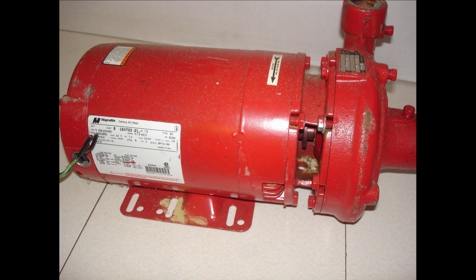This is a 2 horsepower high speed circulator, and there's a story behind this. When I was very young, they would send me out to help contractors. I went out to help this contractor who had this pump. He says, this pump's making a lot of noise. I think we need a new pump. And I said, maybe it's just got the wrong size impeller in it or something, or it's oversized. So on a pump like this, you've got a tapping for a gauge on the suction side and another tapping on the discharge side.